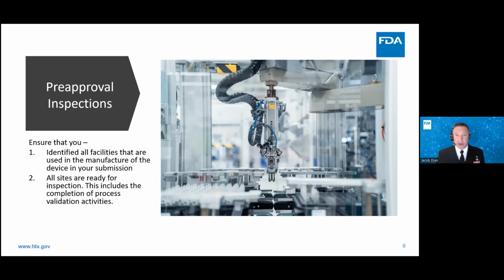Inspections are going to occur when the information submitted demonstrates that the quality system implemented on site appears to be in compliance with 21 CFR 820, and any major deficiencies have been adequately addressed. And thirdly, the site needs to indicate that they're ready for that pre-approval inspection.